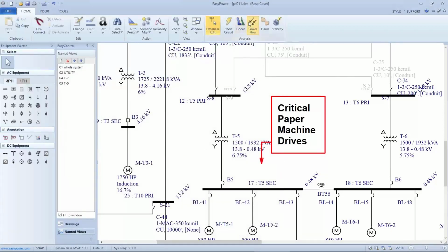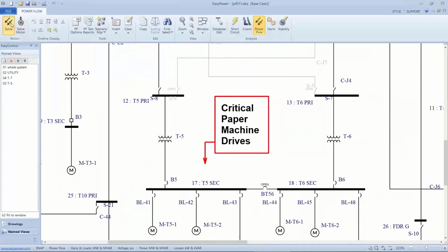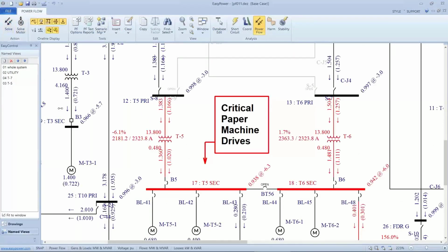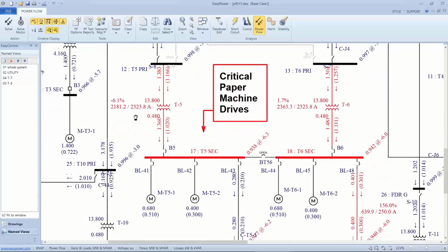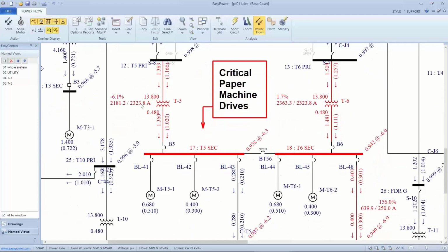And then go back and see what that does to my error reports. Okay, so now it's rated maximum for 2323. It's flagged red because I'm within that 10% range, but at least now it's not being over-dutied or over the threshold. Brings up another question.